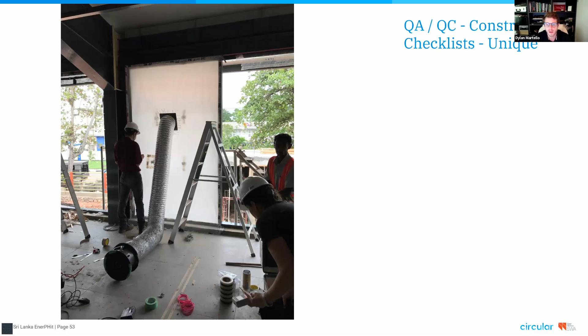This was a big, really critical test for us on this project because we found a key leakage area. What you're looking at is a very specific location, but if we hadn't found and addressed this, we might have had real challenges meeting the whole building blower door test requirements for the project. This was critical, and we did it in the middle of construction.